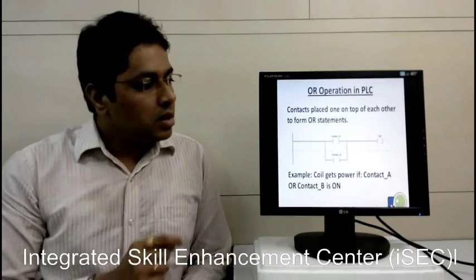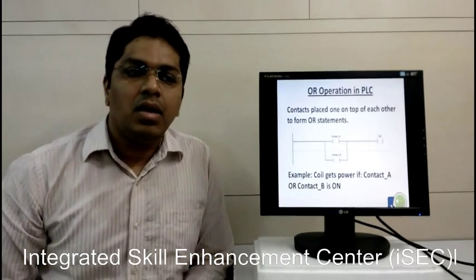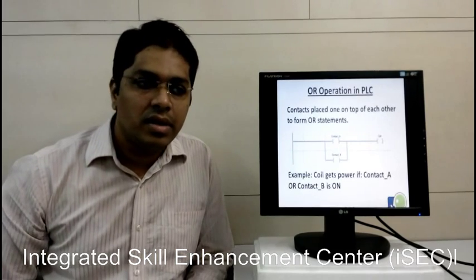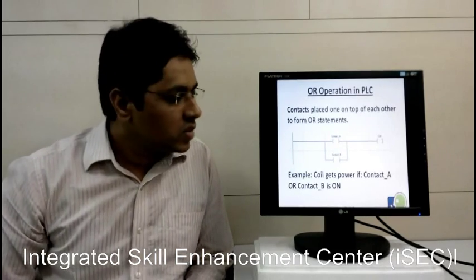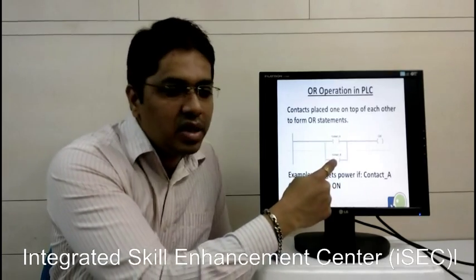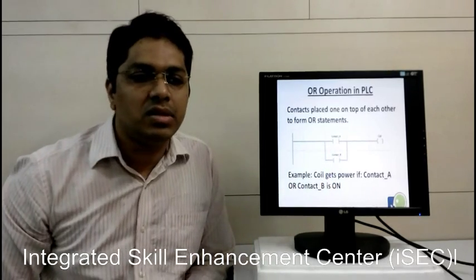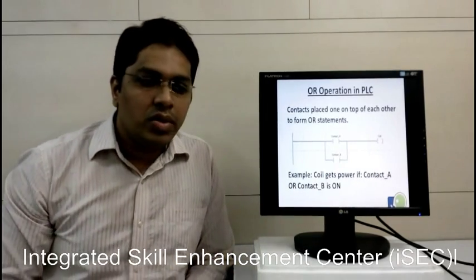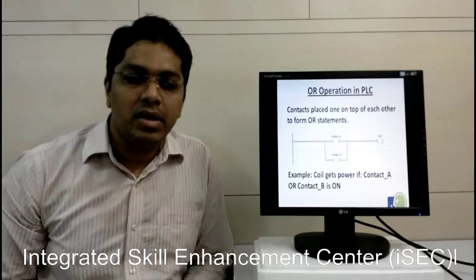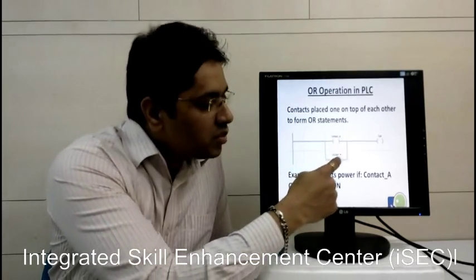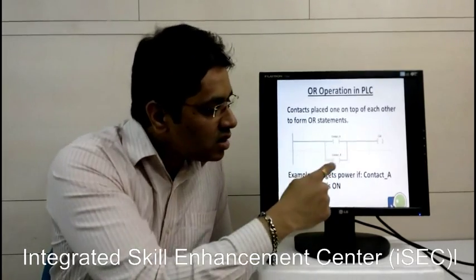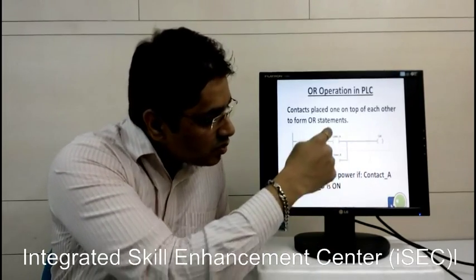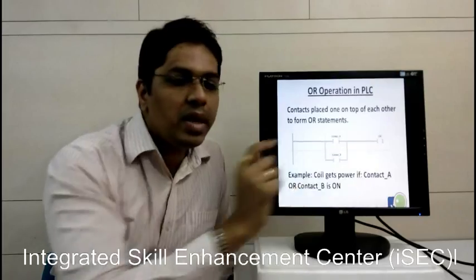Same as that, you can see here as an OR operation. Contact placed one on top of each other to form the OR statement. Contact A and contact B are placed on top of each other showing output as a coil. Here the coil will get powered ON if contact A or contact B is ON. Either one is ON, the output will be ON. If both are OFF, the output will be OFF.